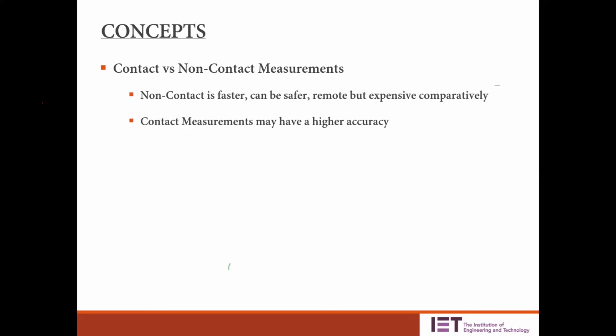We should know that non-contact measurements are fast, safe, and remote, but more expensive, and their accuracy may be lower. Contact measurements, being directly in touch with the target, always give higher accuracy than non-contact ones. But if the target isn't safe to touch, or it's very remote—for example a load break switch about 10 meters high that's energized—you can't reach or touch it. Non-contact measurements come in handy in occasions like those.